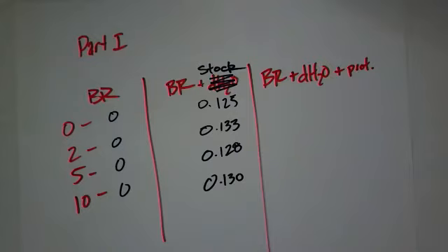In the event that, let's say hypothetically, you get 0.125, 0.947, 0.542, 0.999, in that case, I would say something's wrong with my cuvette, something's wrong with my spectrophotometer, something's wrong with my Bradford reagent solution. I would check with my adjacent lab groups and ask what's happening with yours. Because in the event that it's a cuvette, easy solution, get a new cuvette. In the event that it's the Bradford reagent, then your neighboring groups are going to be having that issue as well. In the event that it's the spectrophotometer, well, then your neighboring groups are not going to have that as well.